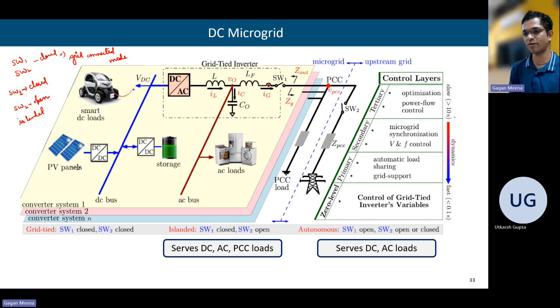You can see the control layers here. Zero level is the control of grid tied inverters and variables, which is very fast, on the order of milliseconds. Primary is automatic load sharing and grid support. Secondary is microgrid synchronization. Tertiary is optimization and power flow control. From this it goes from fast to slow.